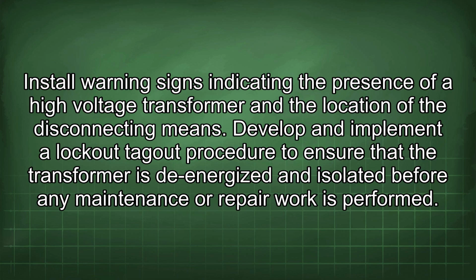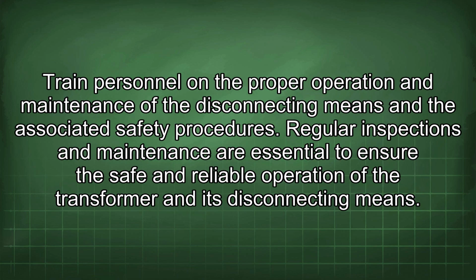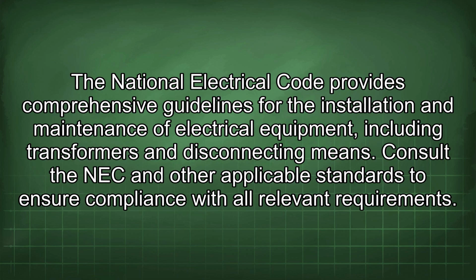Develop and implement a lockout tagout procedure to ensure that the transformer is de-energized and isolated before any maintenance or repair work is performed. Train personnel on the proper operation and maintenance of the disconnecting means and the associated safety procedures. Regular inspections and maintenance are essential to ensure the safe and reliable operation of the transformer and its disconnecting means. The National Electrical Code provides comprehensive guidelines for the installation and maintenance of electrical equipment, including transformers and disconnecting means. Consult the NEC and other applicable standards to ensure compliance with all relevant requirements.